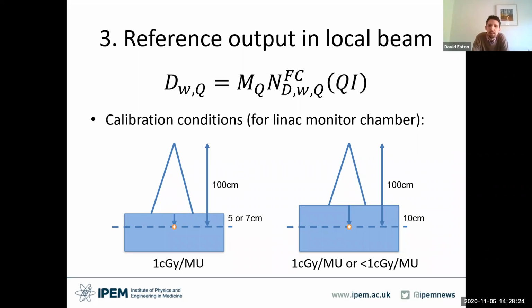But we recognize that some centers may also wish to follow a 10 centimeter measurement depth, which is recommended in the IAEA documents. I think a few centers in the UK are doing this, but we didn't want to be too prescriptive. And equally, you may wish to calibrate your machine so it gives 1 centigray per monitor unit at, say, 5 deep or at 10 deep. That gives you a nice simple result.